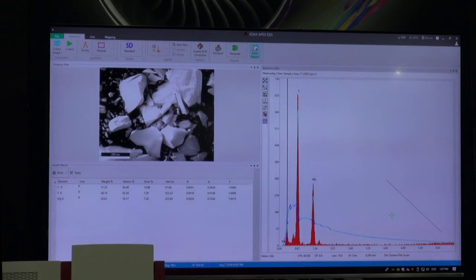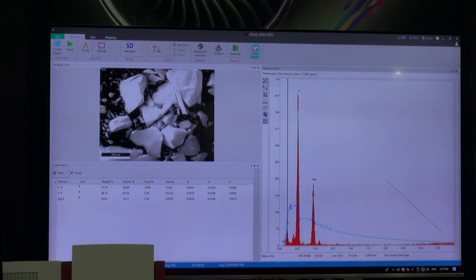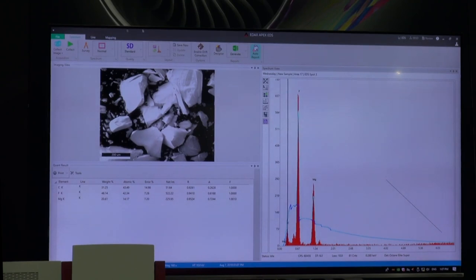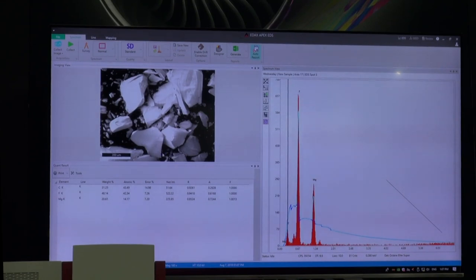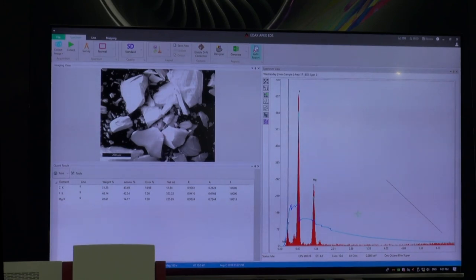With a Bremsstrahlung model using one point in the high energy region, I should be able to calculate the Bremsstrahlung all the way down — and we see this is a horrible fit. This is not because the model is wrong; it's because we have a lot of sample self-absorption. We generate x-rays in this cavity, and most of them are absorbed as they try to escape to the detector through the large particles around them. This misfit is not a modeling problem — it's a sample problem, and it tells you don't click the quant button.